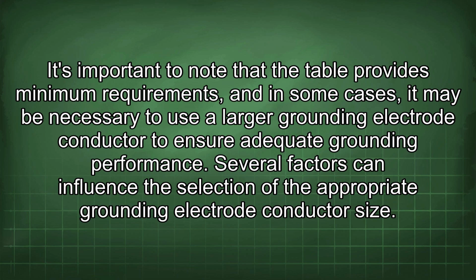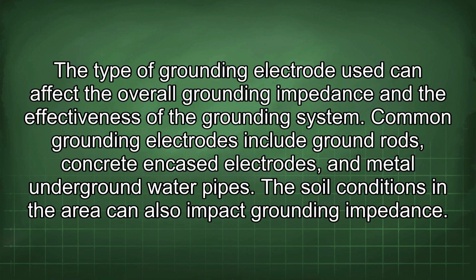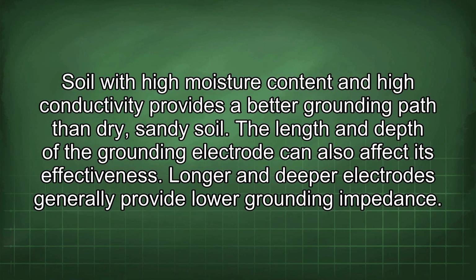Several factors can influence the selection of the appropriate grounding electrode conductor size. The type of grounding electrode used can affect the overall grounding impedance and the effectiveness of the grounding system. Common grounding electrodes include ground rods, concrete encased electrodes, and metal underground water pipes. The soil conditions in the area can also impact grounding impedance. Soil with high moisture content and high conductivity provides a better grounding path than dry, sandy soil. The length and depth of the grounding electrode can also affect its effectiveness. Longer and deeper electrodes generally provide lower grounding impedance.